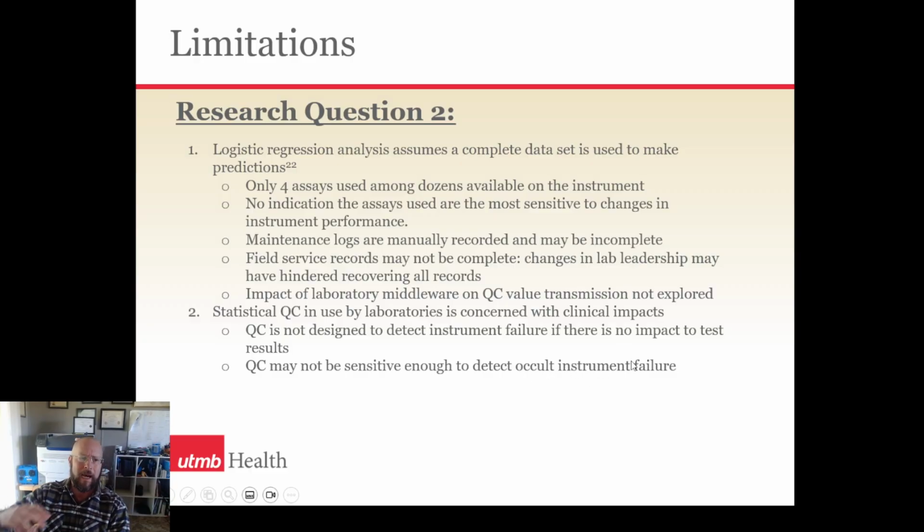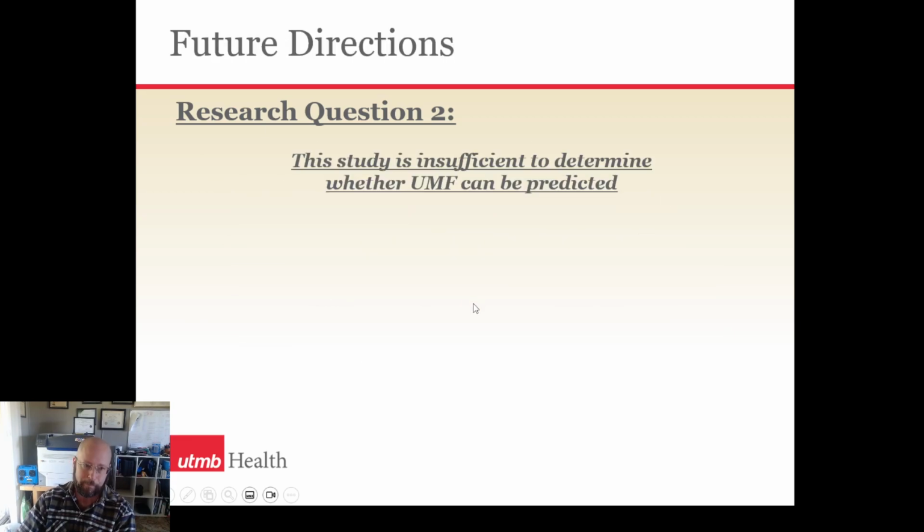Let's say, for example, you could imagine a situation where a sample probe is riding on a bearing surface that's not properly lubricated, and it might shake as it's delivering its volumes. But maybe it's delivering the correct volume. And most people might say, hey, that doesn't matter because you get the correct results, the correct volume. But the reason maybe it's shaking in its bearing surface is because that bearing is worn or improperly lubricated or over lubricated with dust in it, and it's gonna fail. So knowing that minor shaking is occurring might be very important, and QC is not designed to detect those things.